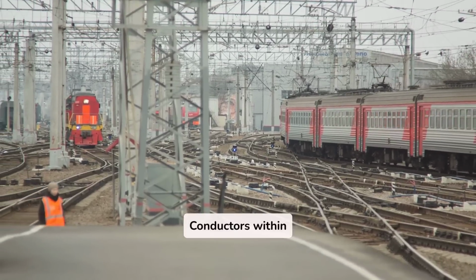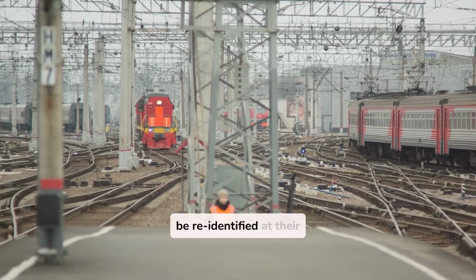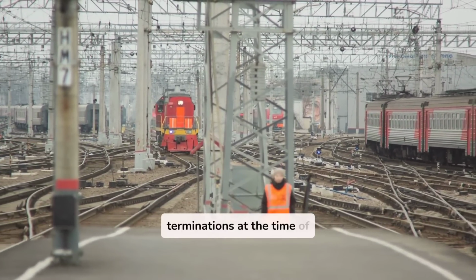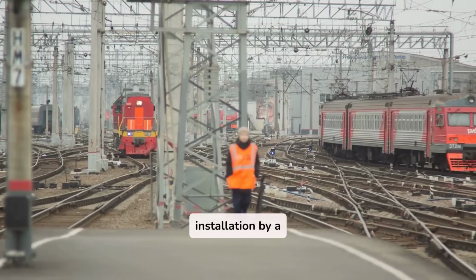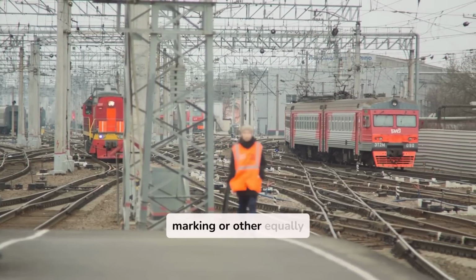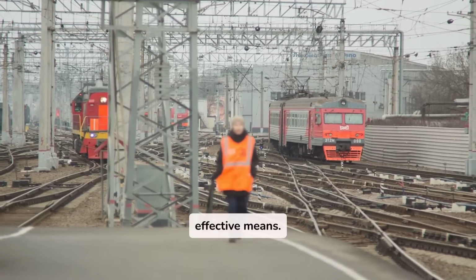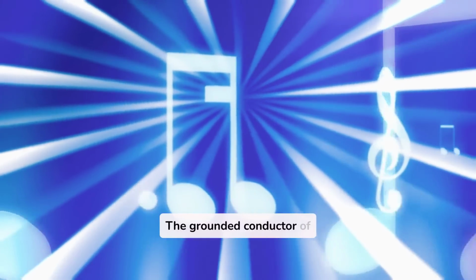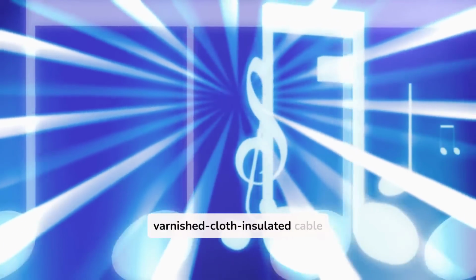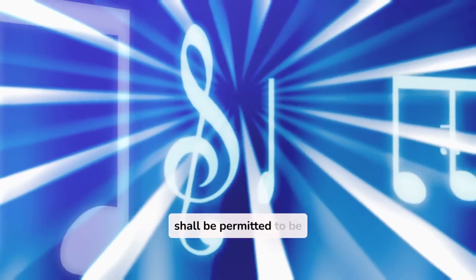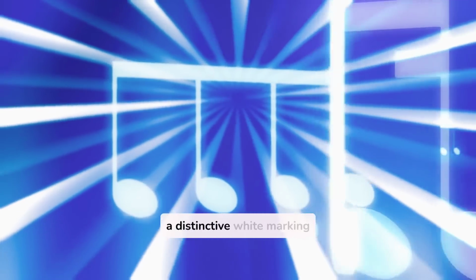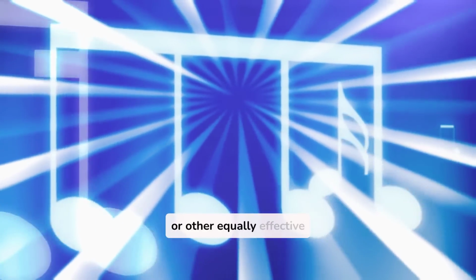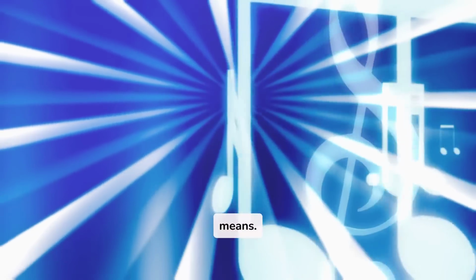Exception No. 1: Conductors within multiconductor cables shall be permitted to be re-identified at their terminations at the time of installation by a distinctive white or gray marking or other equally effective means. Exception No. 2: The grounded conductor of a multiconductor varnished cloth insulated cable shall be permitted to be identified at its terminations at the time of installation by a distinctive white marking or other equally effective means.